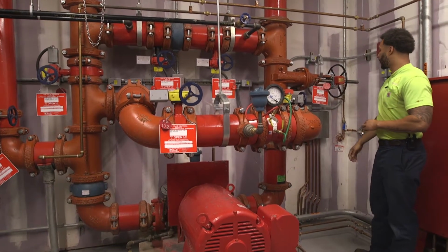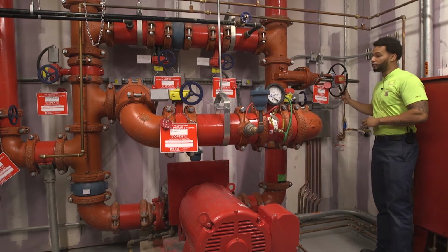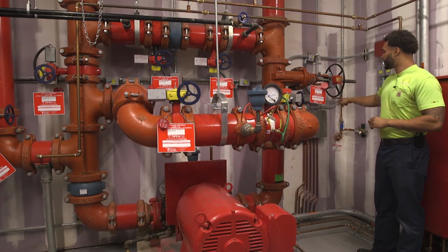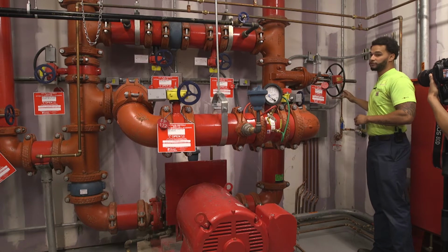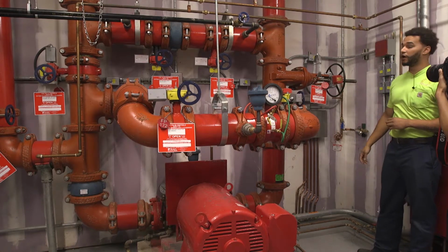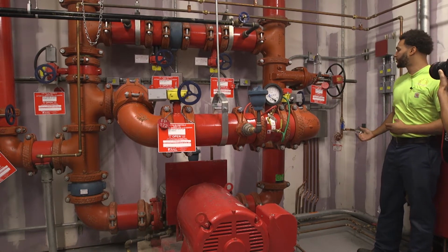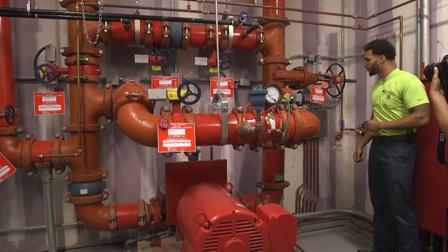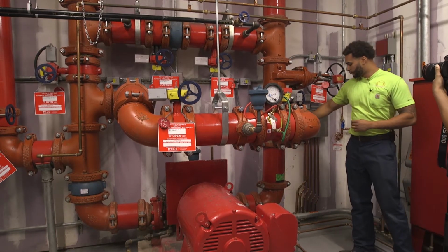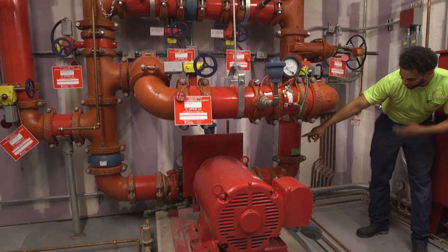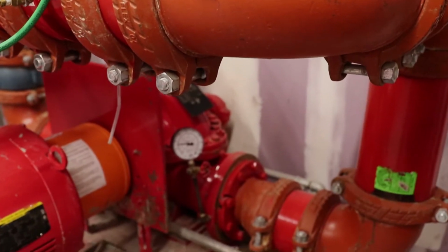So now we're looking at the suction side. We're looking at our suction side isolation valve, which is the OS&Y valve. This valve is tampered, so anytime someone opens or closes this valve, you will get an alarm at your fire command station indicating someone is messing with the valve. We're going to flow downwards, and we're looking at our suction side gauge here. We have about 63 pounds coming into our system.